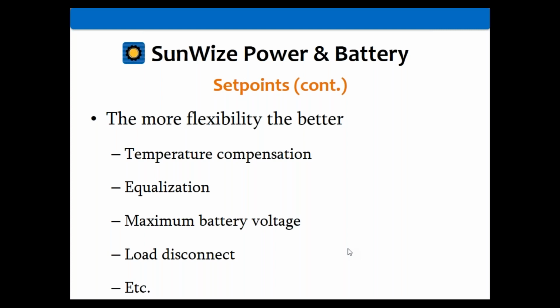Max battery voltage - I mentioned that before with the high voltage problem. It's nice to be able to set that so it can be limited, as well as adjusting the max temperature compensation. Getting back to temp comp again, not just changing the coefficient itself, but perhaps setting limits. Some manufacturers, like Deca batteries for instance, will want temperature compensation but want to limit it - on the high end to something like 50°C, they don't want to adjust past that, and on the low end around 0°C, they don't want to adjust past that either. So some manufacturers actually want to set limits for temp comp, and it's nice to be able to do that too. It just helps get that battery a little extra life.